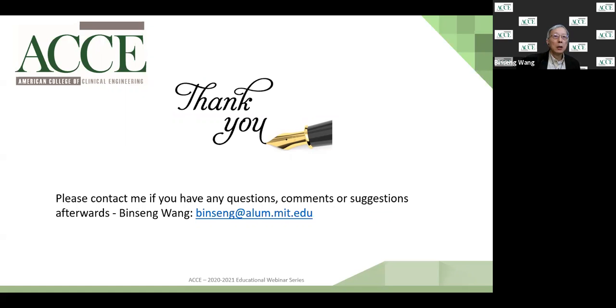Okay, so the lesson here is that first, there's nothing you can do to calibrate or recalibrate that flow meter or vacuum regulator, etc. If it breaks, you replace it most of the time. Maybe sometimes you can do a little bit of cleaning because there is some dirt in there. But otherwise, don't bother to schedule maintenance there. Repair if possible, otherwise replace. Okay. Now, coming back to defib.